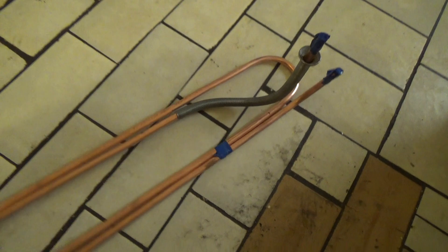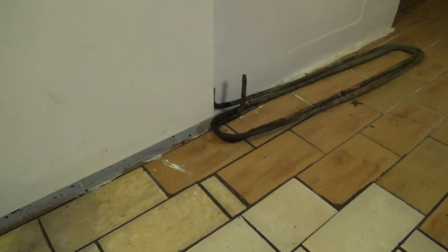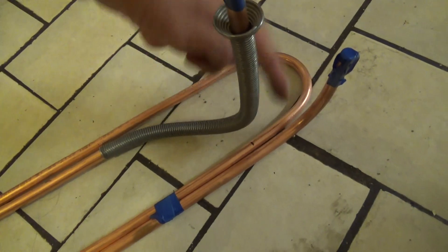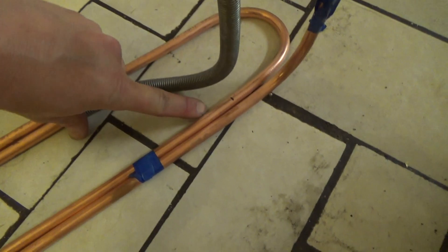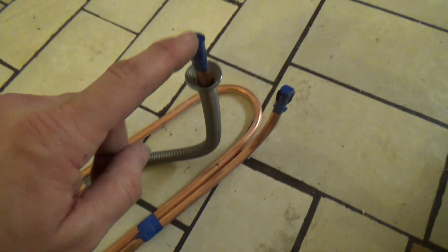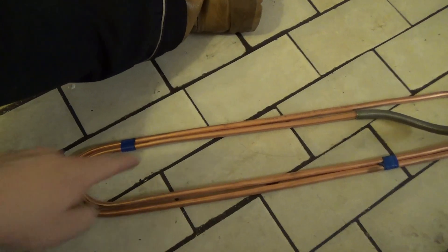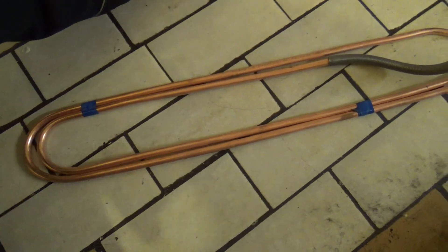I've got that made. This pipe here went all the way to the end, came in and then came up — that was too tight a bend for me to do with the spring, so I've just taken a shortcut across to here. It's not going to make any difference as long as these come up in roughly the right place. I might put a couple of blobs of braze just to join the two coils together so they don't rub.